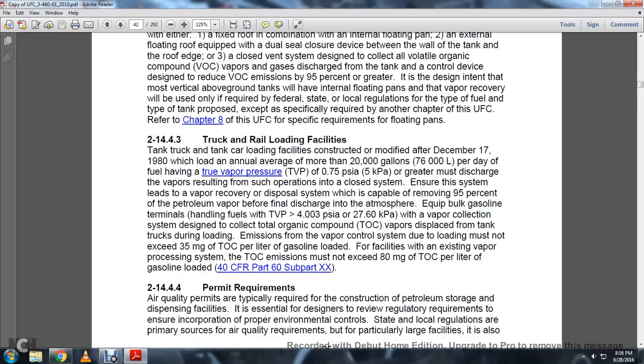Alright, 2-14.4.3 Truck and rail loading facilities. Tanker truck and tanker car loading facilities constructed or modified after December 17, 1980, that load on an annual average of more than 20,000 gallons per day of fuels having a true vapor pressure of 0.7 psi or 5 kPa, the loader must discharge the vapor resulting from such operation in a closed system, ensuring the system leads to vapor recovery. The disposal system is capable of removing 95% of the petroleum vapor before final discharge into the atmosphere.